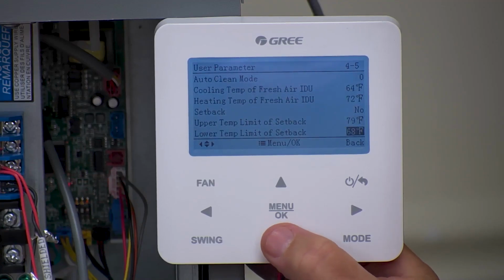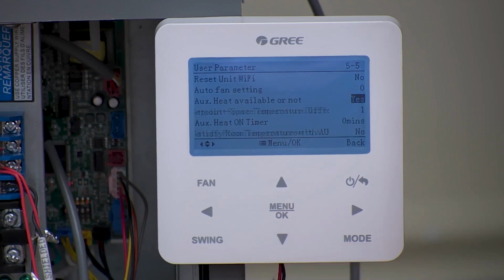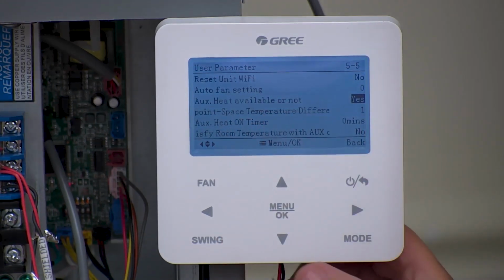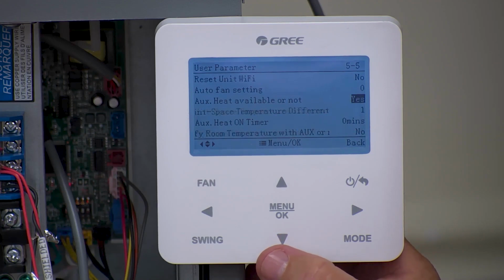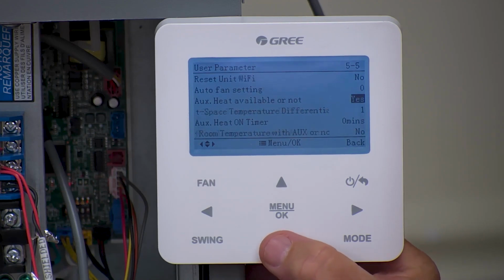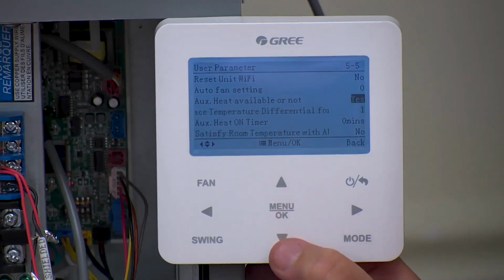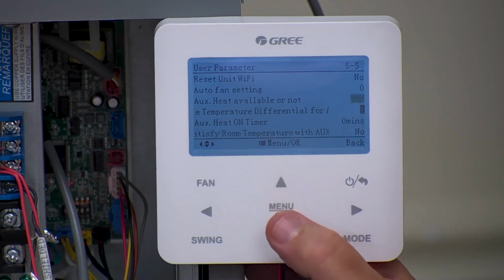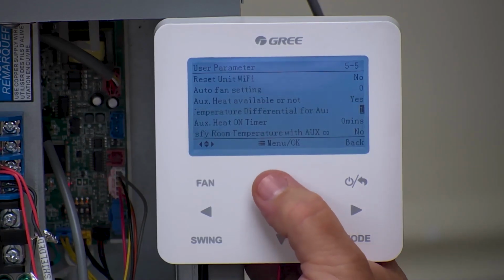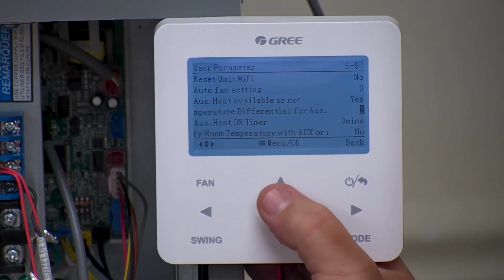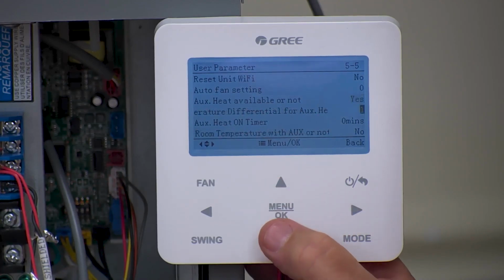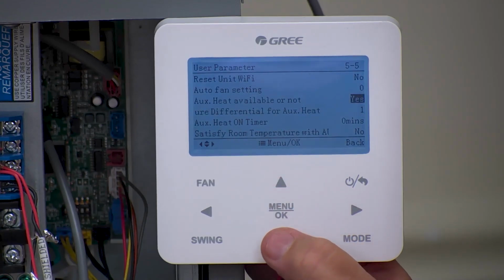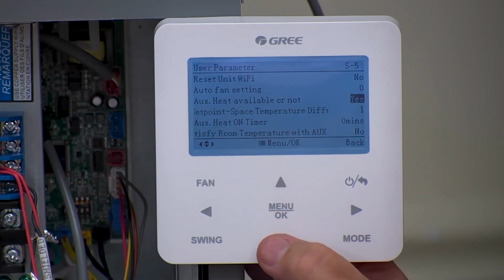Let me get there. Auxiliary heat available or not, yes or no. Like I said, if you've got electric heat, that's going to automatically populate yes. If for some reason it doesn't, it should at least give you that and you can set it. Space temperature differential. So it's kind of a weird setting for you. And if you notice I'm going up and down with the arrow buttons, that's because these things time out rather quickly and you're going to lose your page. So if you don't want to lose your page and you're trying to focus on something, just keep hitting up and down or left and right and it'll keep you there until you're ready to move on.